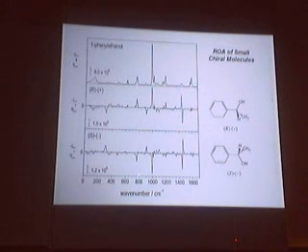With VCD the lowest you can get is something like 800 to 1,000 wave numbers, so they just have that region there, first of all because you need different optical elements for different ranges of the vibrational spectrum. Whereas with Raman, this is the big advantage of Raman generally. You're analysing visible scattered light with a visible spectrometer. It's all visible, so you get the whole vibrational spectrum. We get down to below 100 here, and you can actually go up to over 4,000 wave numbers on the same instrument using a multi-channel detector.